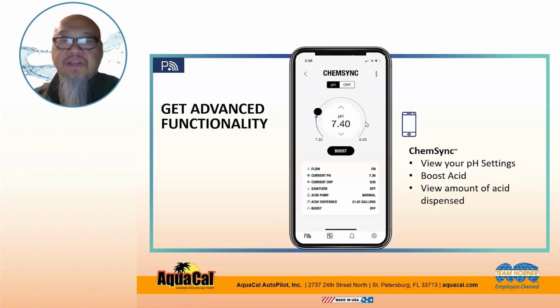On the pH screen, let's take a look at this one. The set point is at 7.4. On this particular unit, we've got the boost mode. When you press the boost, it gives you another screen that asks you how many ounces of solution you want to feed into the system. It will override the on and off of the acid pump and leave it on until that amount of volume has been fed into the system. So it's giving you an overall view of what your set point is.